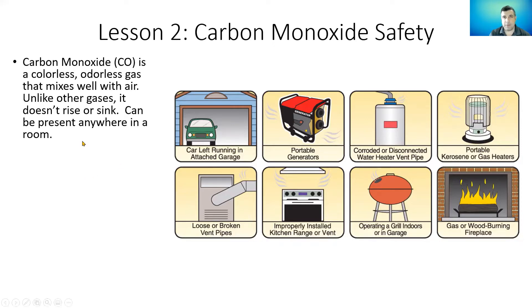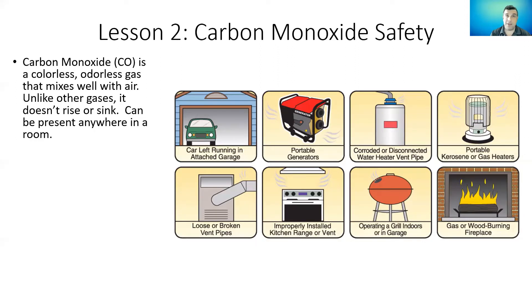What is carbon monoxide, or CO? Don't get confused with carbon dioxide or CO2. Carbon monoxide is a colorless, odorless gas that can be present whenever you light a fuel — like natural gas, propane, or oil — on fire, like what we do in HVAC equipment. Unlike other gases, it's pretty much the same density as air, maybe slightly lighter. So it's not really going to rise or sink — it's going to move around freely with the air in a room and can be present at any elevation in the house.